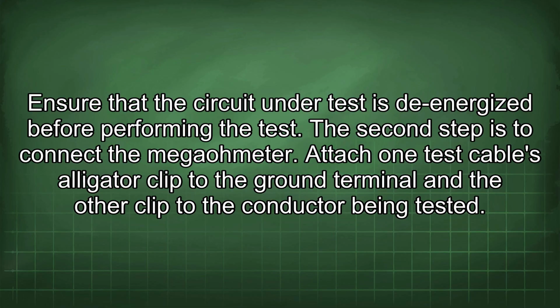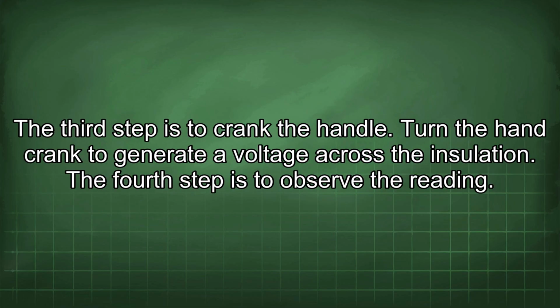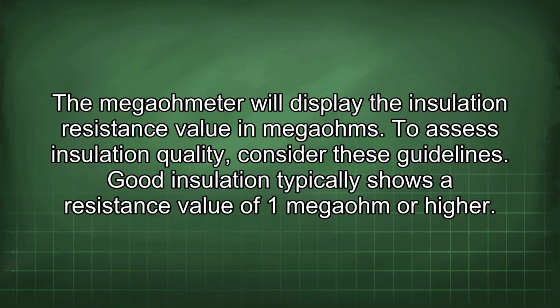The second step is to connect the megaohmeter. Attach one test cable's alligator clip to the ground terminal and the other clip to the conductor being tested. The third step is to crank the handle. Turn the hand crank to generate a voltage across the insulation. The fourth step is to observe the reading. The megaohmeter will display the insulation resistance value in megaohms.